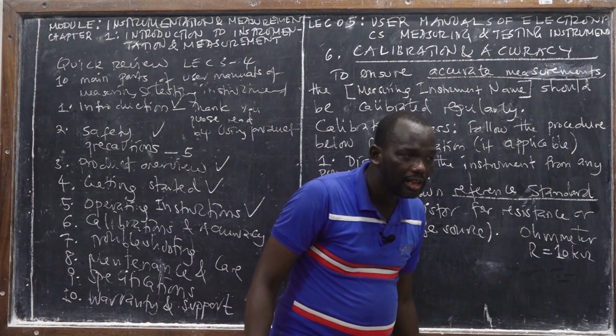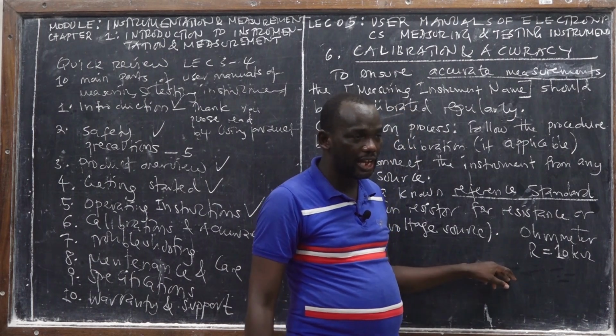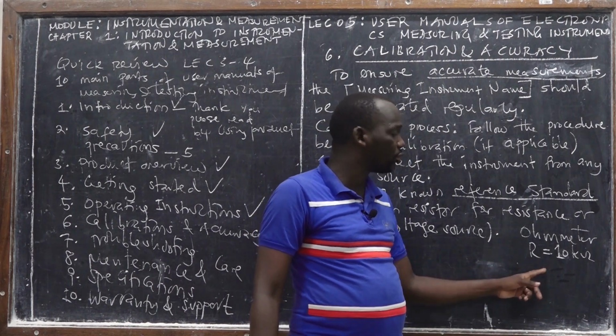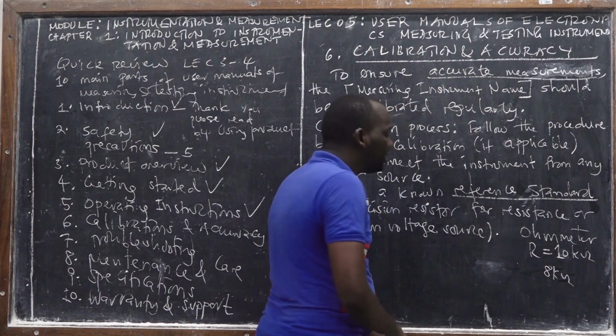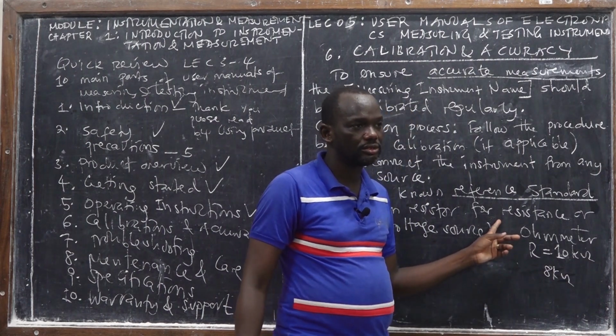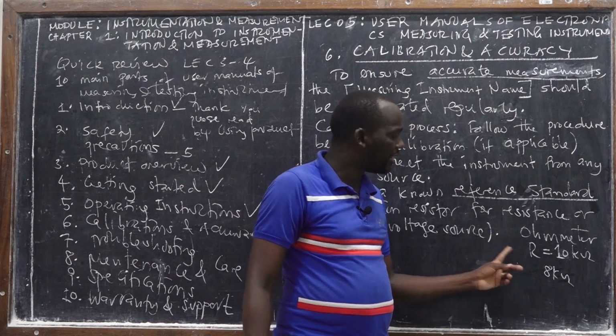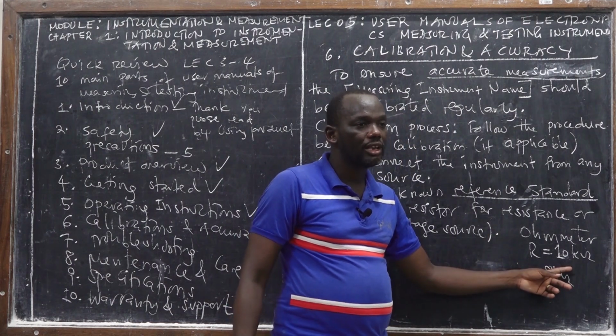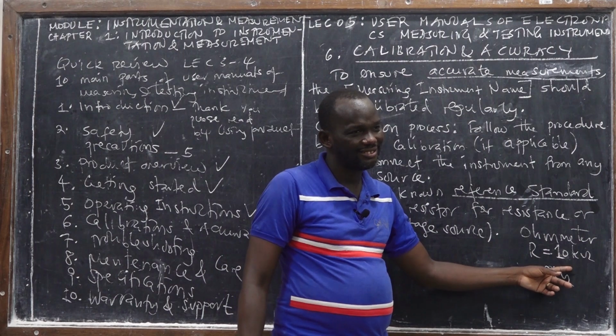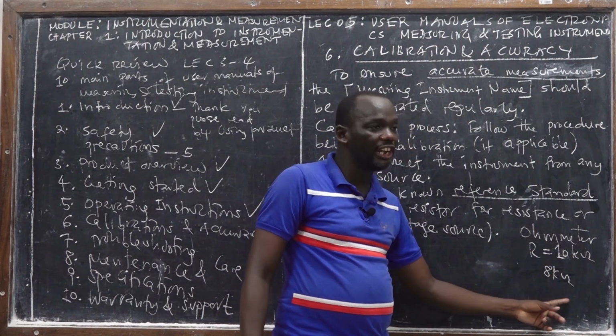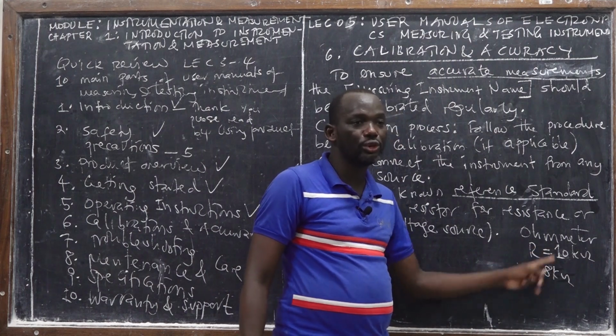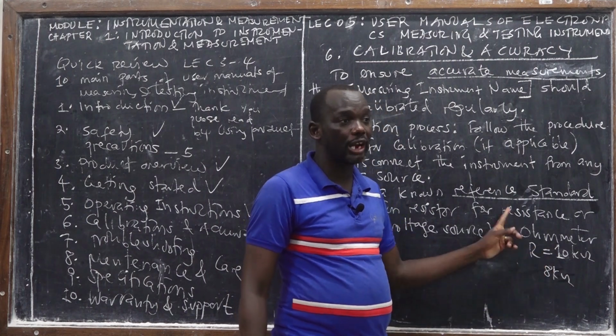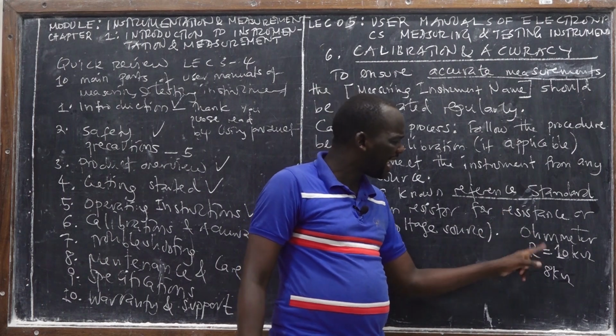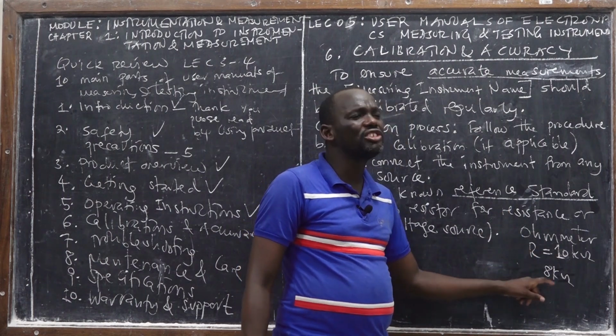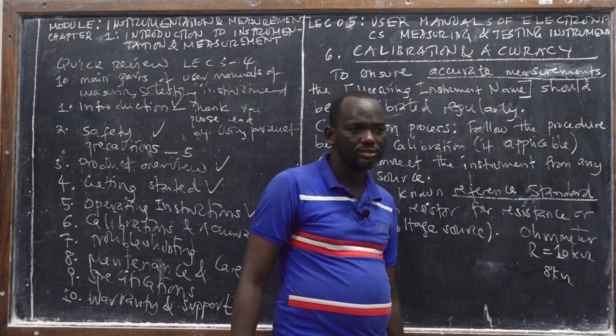Are we together? So in case you use that digital ohmmeter and measure the resistance, which is expected to be 10 kilo ohm, and maybe you measure 8 kilo ohm, then this instrument needs to be calibrated, because the standard resistance is 10 kilo ohm. What is the deviation? 2 kilo ohm. So you have to calibrate. You'll know that this digital ohmmeter is not calibrated because it's giving wrong readings.